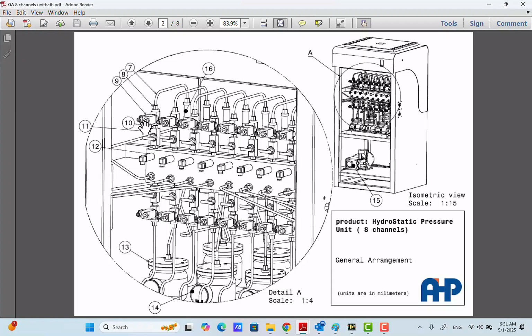The amount of flow to the sample piece is set using these needle valves. Whenever you have big samples, you can open this needle valve more to have more flow to the sample piece. Or if you want to do a burst test on a sample piece, you need to open these upper needle valves more to have more flow of water to the sample piece. Whenever you have a very small sample piece, you need to close this needle valve completely and open it for 1 or 2 degrees. This means that you will allow a very low amount of water to enter the sample piece. This will help precise adjustment of the pressure inside the small sample pieces. I mean, the upper needle valves are important for fine tuning of the pressure inside the sample.